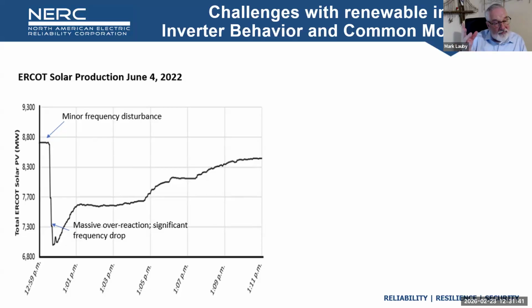But that's for new ones. For existing panels, there's still a worry. Another thing we've seen with inverter-based resources is they don't necessarily provide an ability to absorb or provide reactive power as much as they could. They're really tightly banded based on what the manufacturer sets. What we learned in Spain is you need to open them up. They need to be able to support voltage with reactive power, either absorbing it or providing voltage or VARs. That was one of the fundamental failures in Spain.